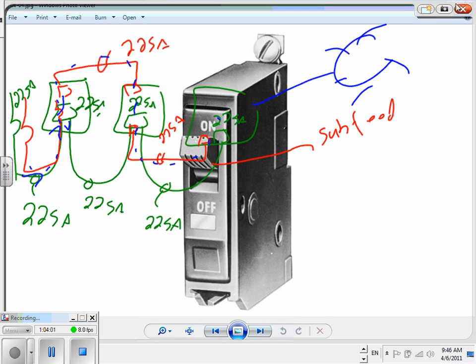What's the problem with this? Expensive. But with the 2008, guys, you can do it, because you can have one feeder, a 225 amp panel, a circuit breaker feeding a feeder to a panel that goes from here all the way to the bottom with 84 circuit breakers in it. That's a good system. You can feed a lot of stuff from 84 circuit breakers. So that's what I wanted to talk about, guys. One thing I want to talk about is the power circuit breakers, which we will come to.